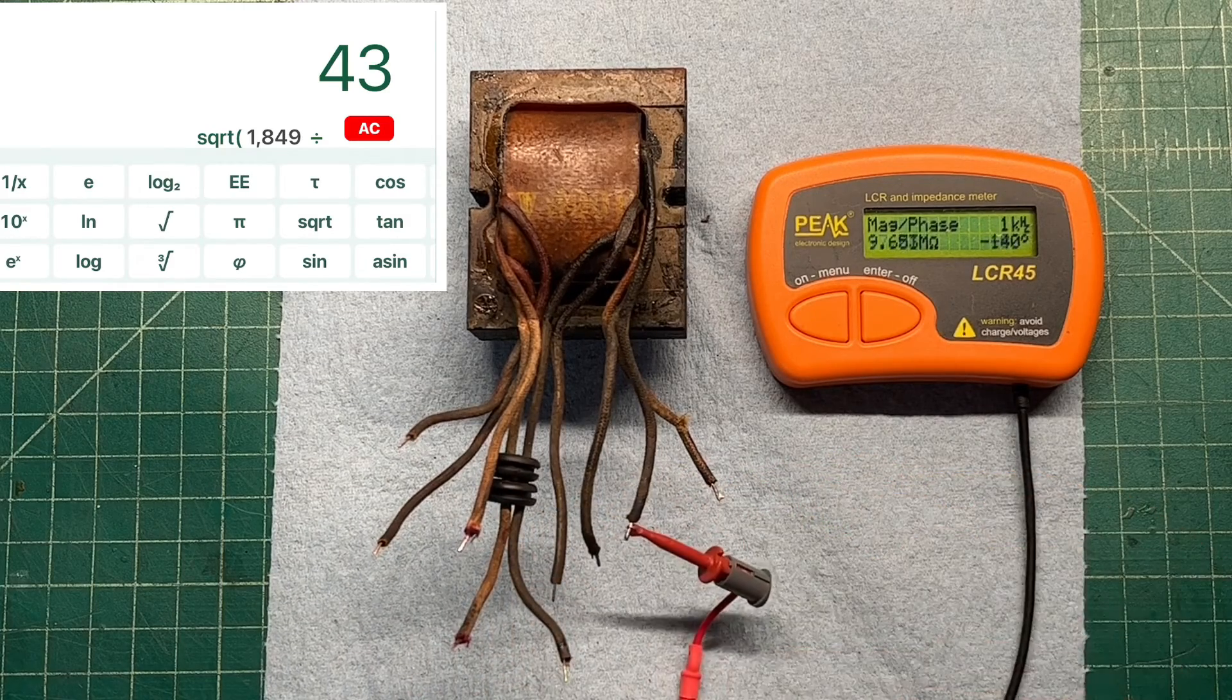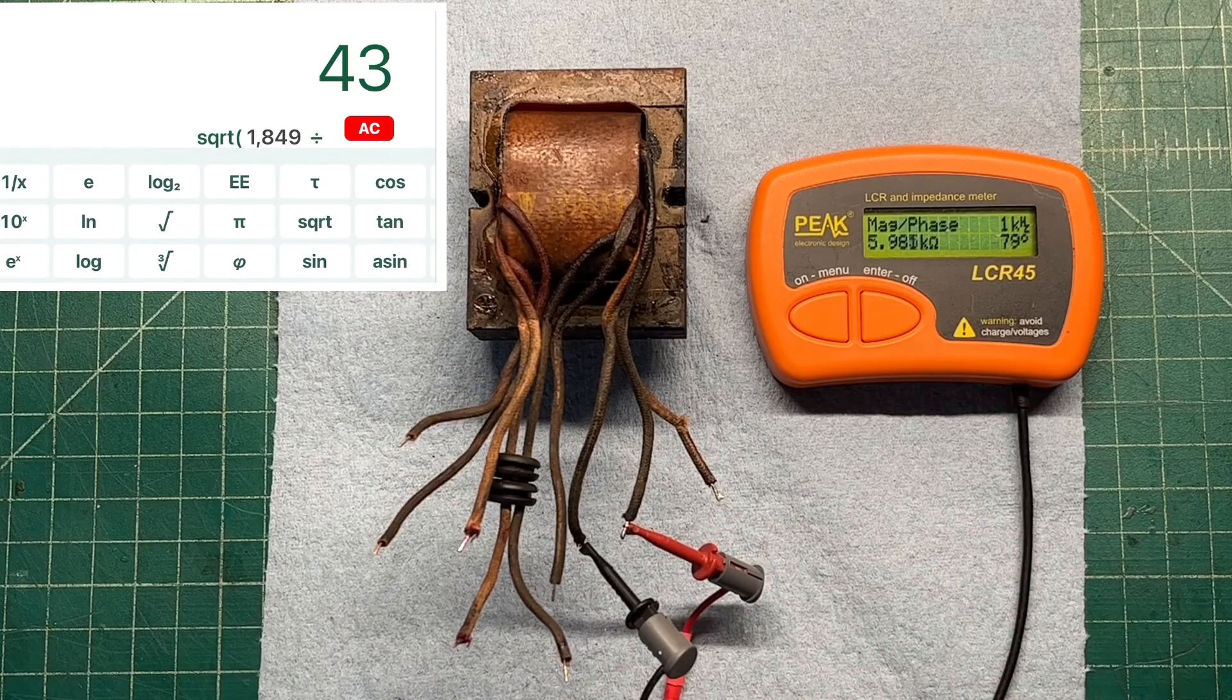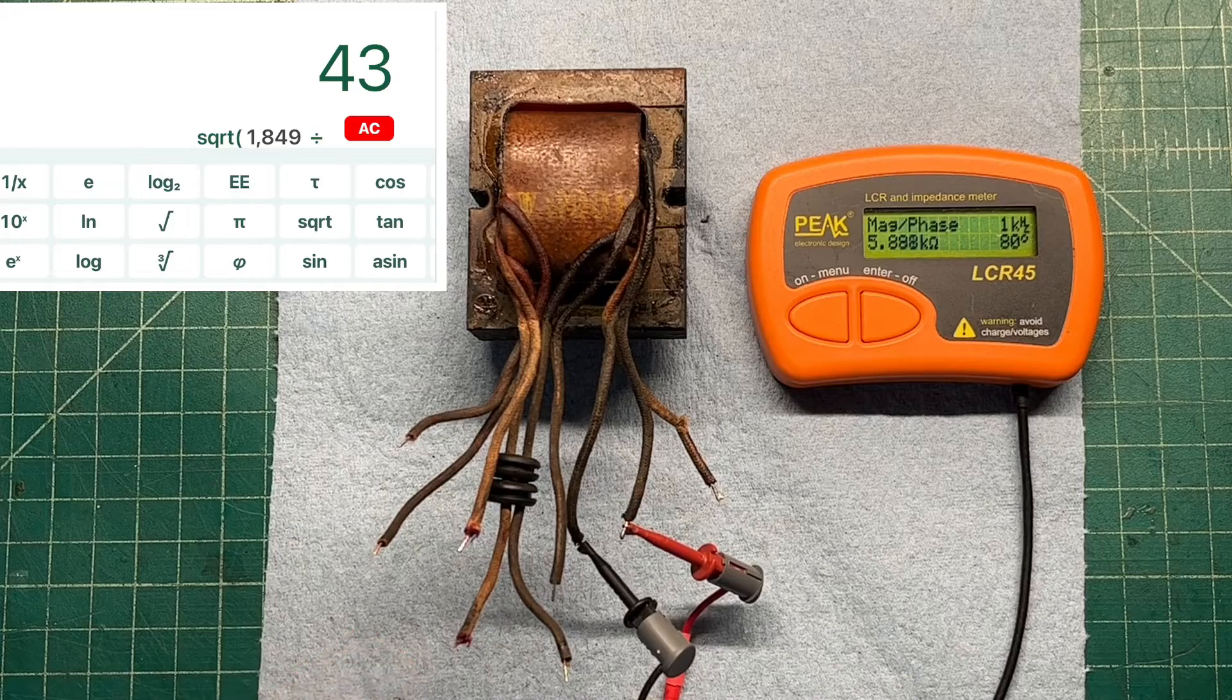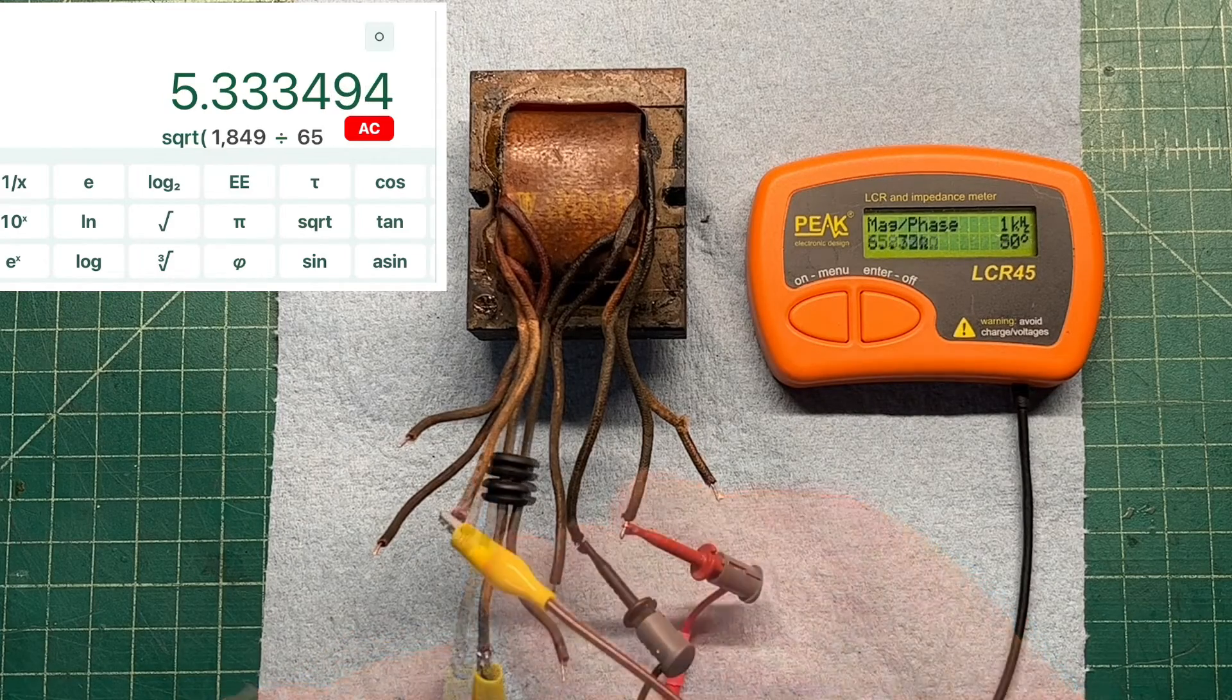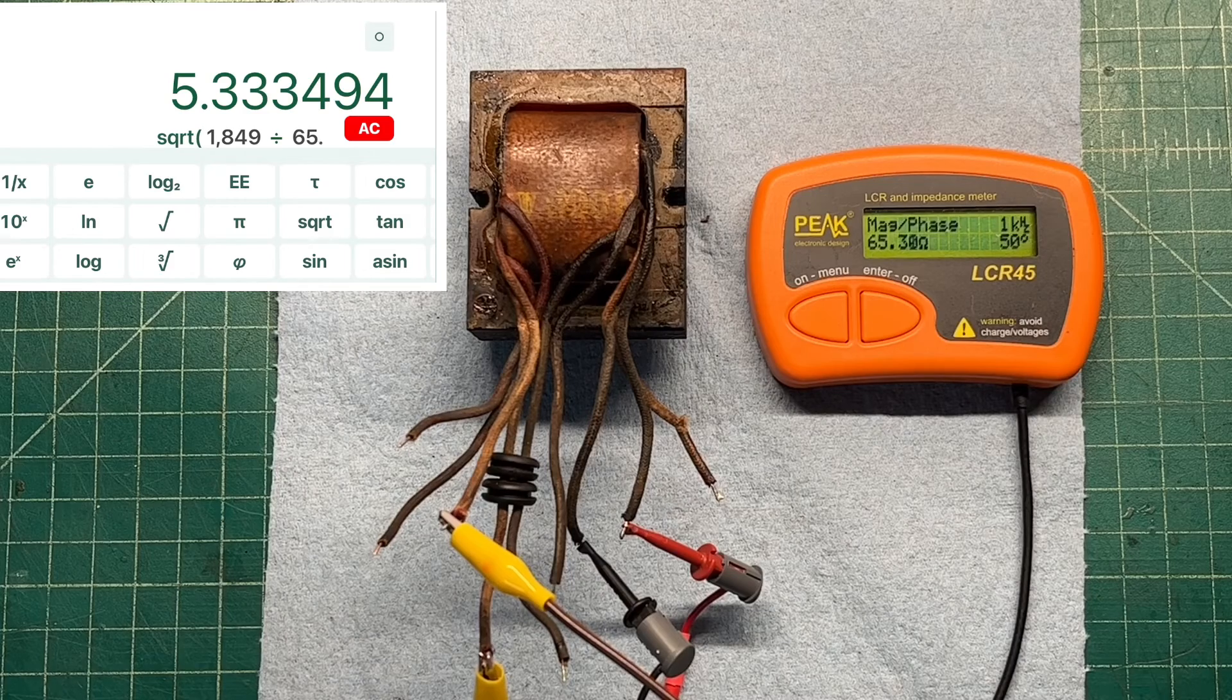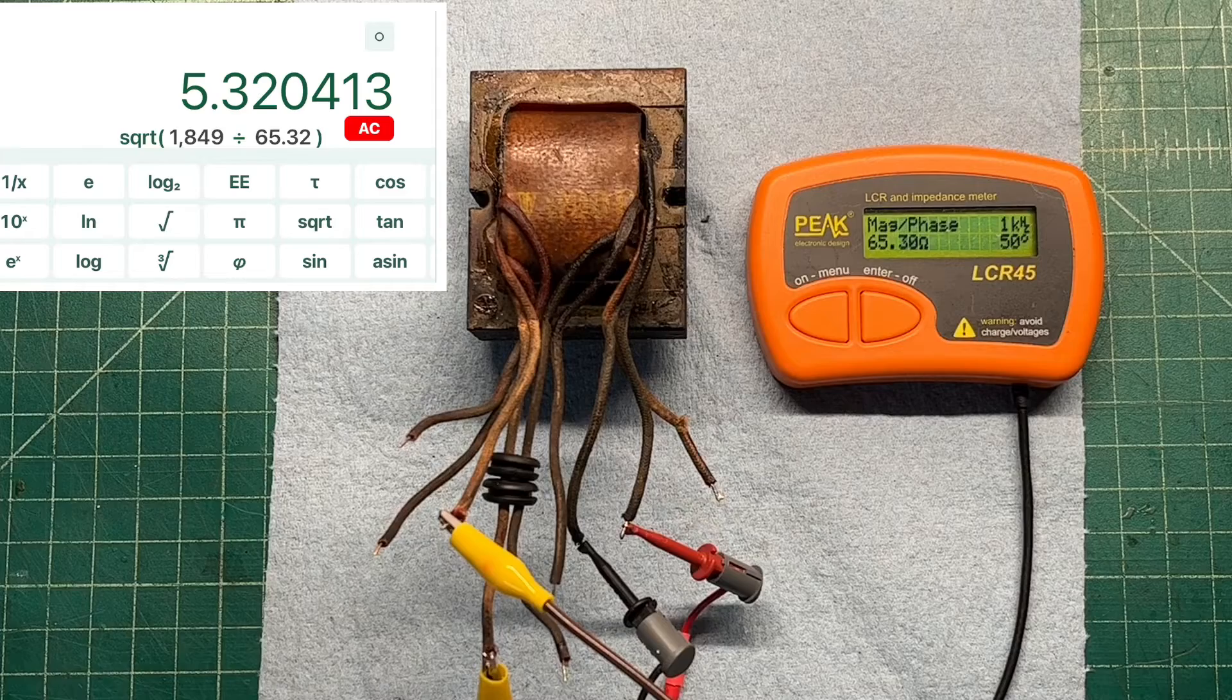So same drill here. I'm going to go back to the primary side. So I'm going to short out the entire high voltage winding here in 6532. And you can see that gives me a turns ratio of about 5.32.